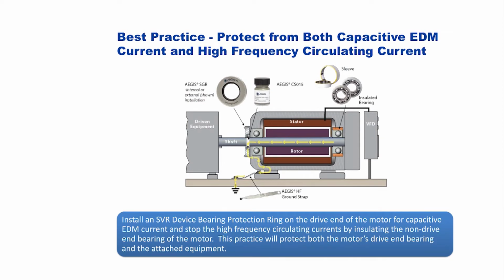Install an SBR device, bearing protection ring, on the drive end of the motor for capacitive EDM current, and stop the high frequency circulating currents by insulating the non-drive end bearing of the motor itself.